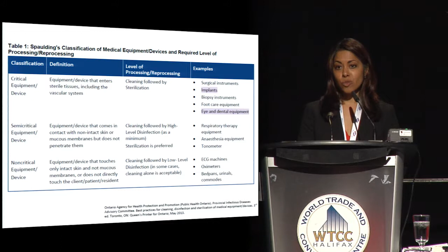When we talk about errors themselves, quite often we refer to them as an endoscopy error, a reprocessing error, a cystoscopy device reprocessing error. So it can be referred to as a problem on the level of whatever procedure or types of instruments are involved. But you can also refer to it as primarily a cleaning problem, high-level disinfection or sterilization, depending on what the need is of the instrument. And I put here, just as a way to frame what I'm going to be talking about, a quick note on the reuse of single-use devices and reprocessing of them. I'm not going to talk much about this, and it isn't really a reprocessing error per se, but I think there are some common themes in terms of the risks associated with that, and I wanted to bring some of that up later.